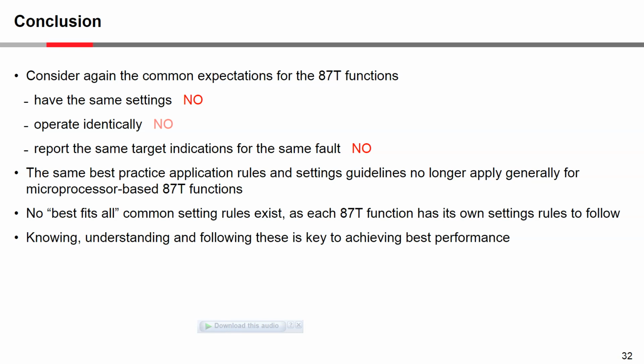So the same best practice application rules and setting guidelines are no longer applied generally for microprocessor-based 87T functions, because it was kind of standard practice before, with the pre-microprocessor generation, that with a delta Y transformer the delta side would be the phase reference. On the Y side, you would have the delta connection of the CT, and that's how you would do it.